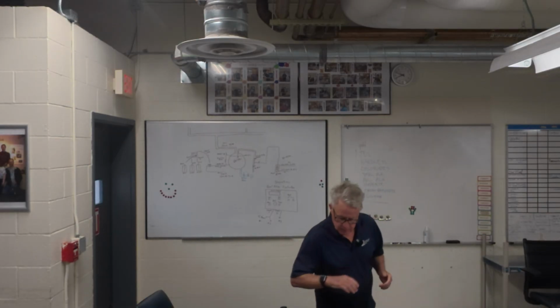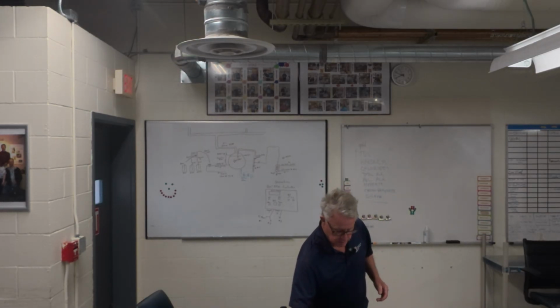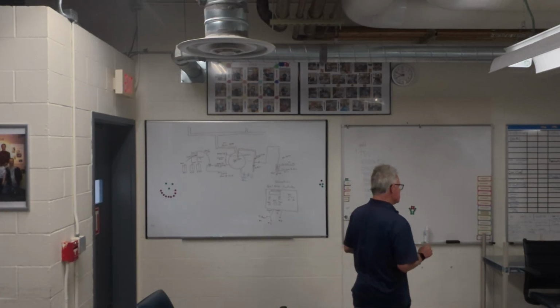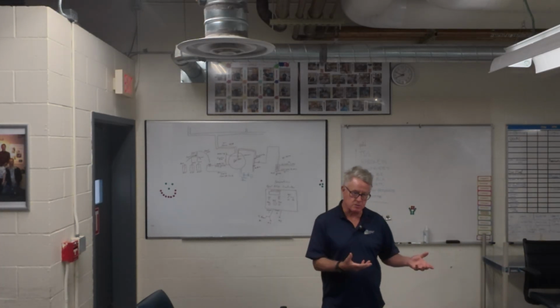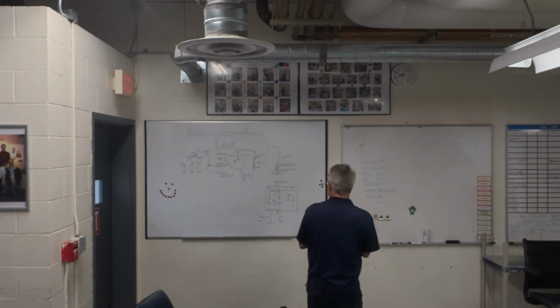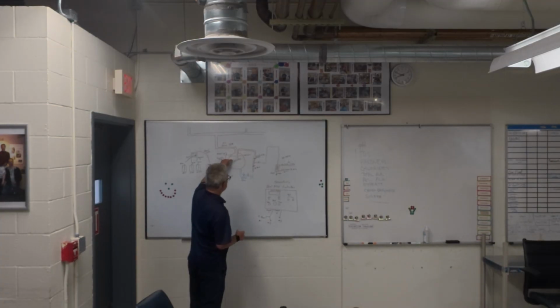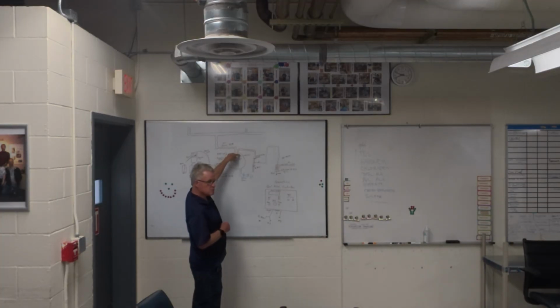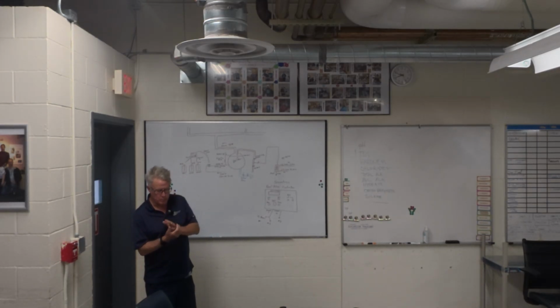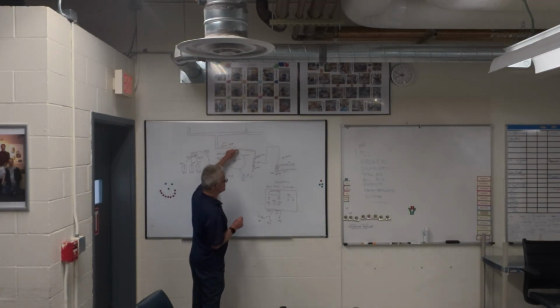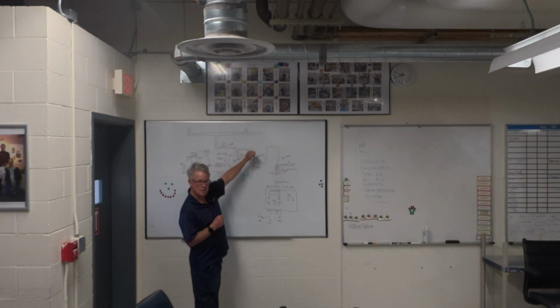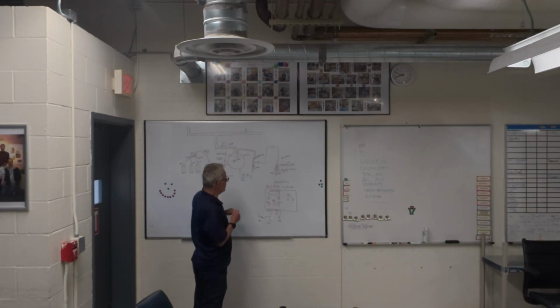And I have the SDS sheets here on the back. There's three types of chemicals that are being used in this. One's a boiler compound, one's an oxygen scavenger, and the other's a steam line. As the boiler creates steam, carbonic acid starts to develop in this boiler. That goes through the steam line. So there's two types of chemicals. The oxygen scavenger and the boiler compound are water soluble. The steam line chemical is not water soluble. We don't want it to be, because we want it to carry in the steam and neutralize the acidic nature of that steam to protect your steam lines from corrosion. Okay? So that's the goal of that one.